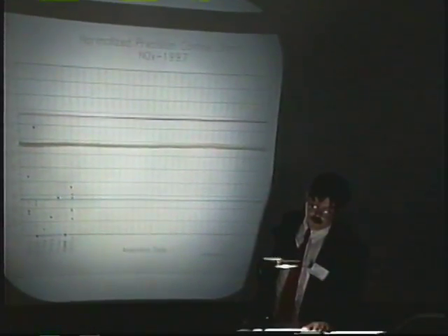Because we're using the absolute value with a precision chart, we don't have any negative area. So we're looking at 0, the average range of replicates, an upper warning limit, and an upper control limit. And again, as things get outside of the control limit, we have to redo the analysis.